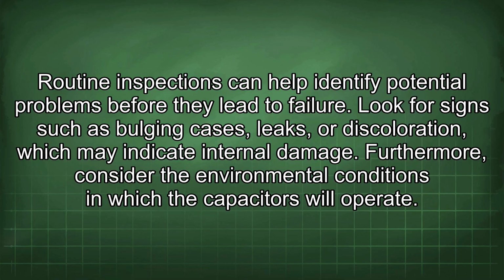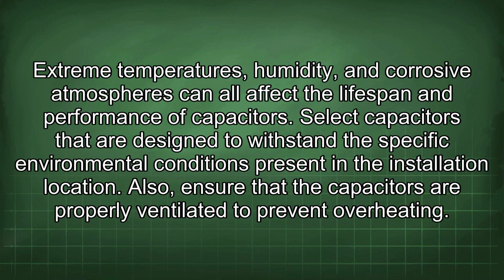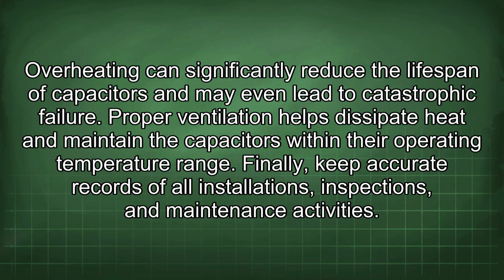Furthermore, consider the environmental conditions in which the capacitors will operate. Extreme temperatures, humidity, and corrosive atmospheres can all affect the lifespan and performance of capacitors. Select capacitors that are designed to withstand the specific environmental conditions present in the installation location. Also, ensure that the capacitors are properly ventilated to prevent overheating. Overheating can significantly reduce the lifespan of capacitors and may even lead to catastrophic failure. Proper ventilation helps dissipate heat and maintain the capacitors within their operating temperature range.